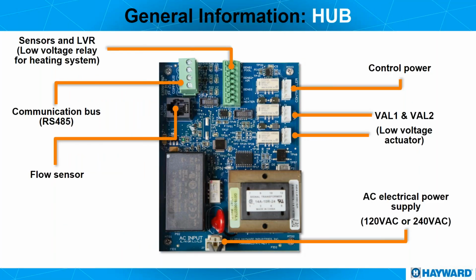And then the hub itself on the inside, which is the board that has all the connections, the low voltage connections. What are those? Well, let's start with the bottom. The bottom is going to be the feed. This part right here, that's going to be voltage that we steal from the connection of the variable speed pump in this case. Remember, this takes the place of the time clock. So there's got to be some kind of voltage coming in, and then after that it goes to the pump.